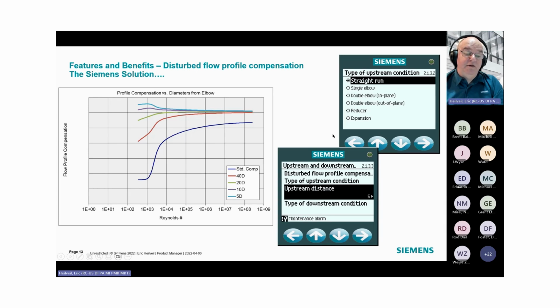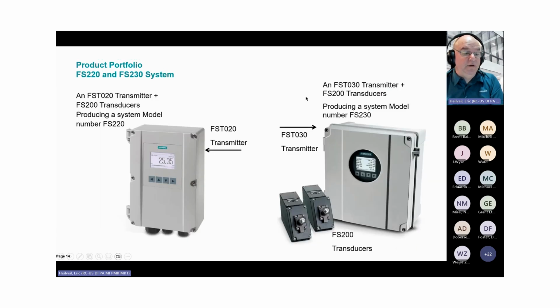And this is actually how you go and protect it. So it's the disturbed flow profile. You tell it what's your upstream distance, what do you actually have in your line, single elbow, double elbow, etc., in plane or out of plane. And the meter will correct for that. So we prefer to have the installation done the way the book says, but the reality of the world is that rarely gets to happen. And this system is built for real world applications. So the disturbed flow profile system allows you to install it where you need it, not where the meter wants to be.